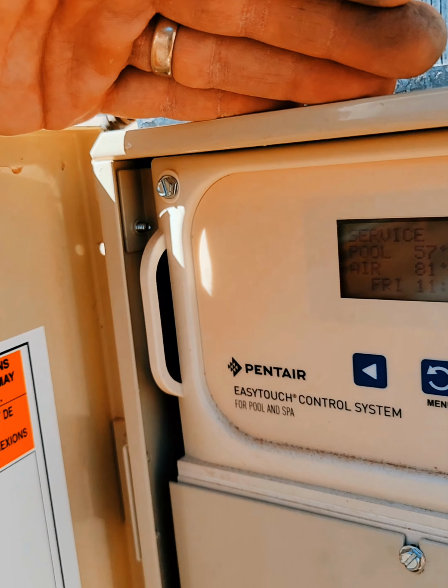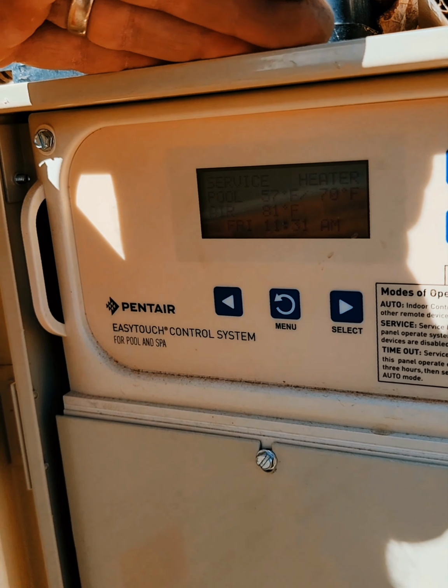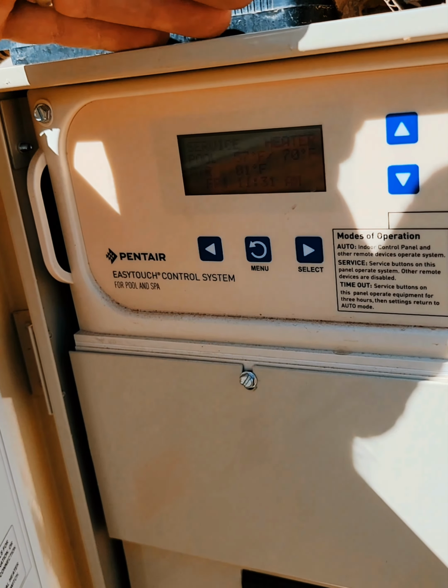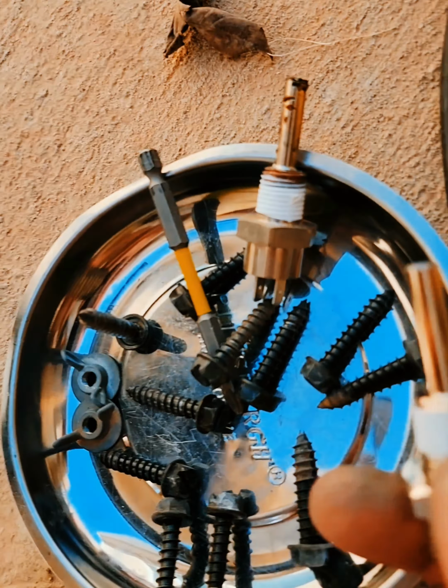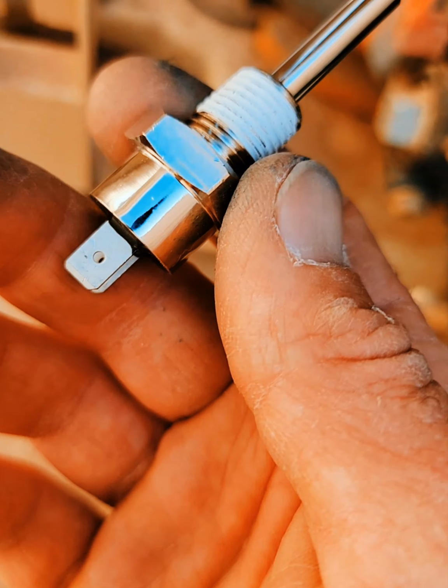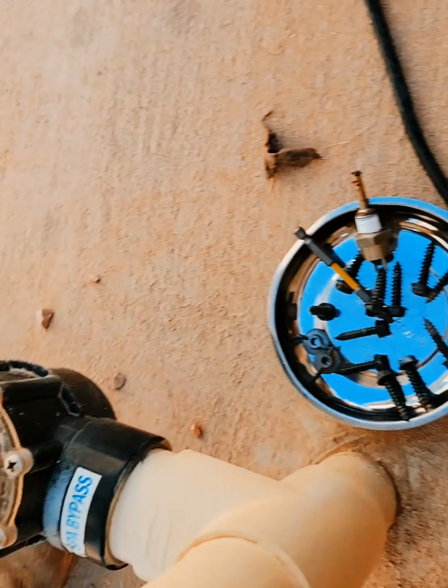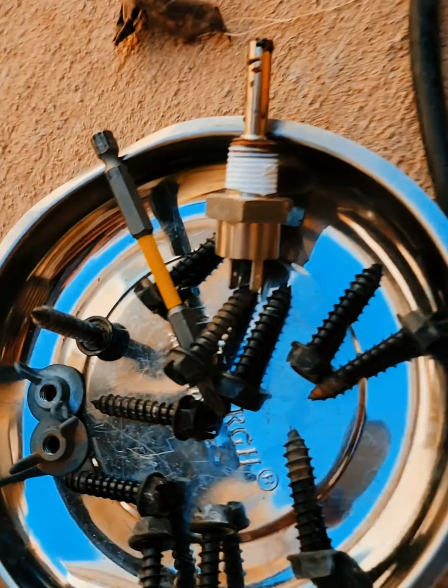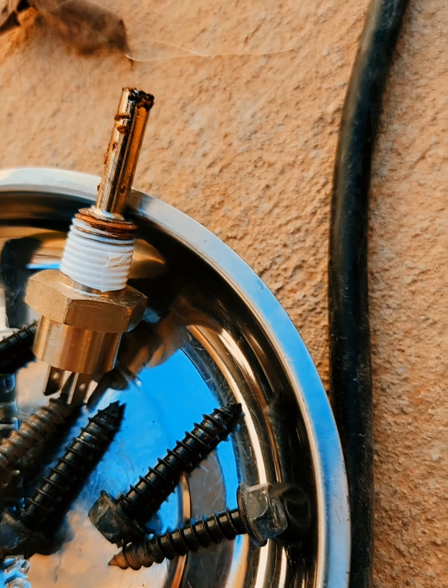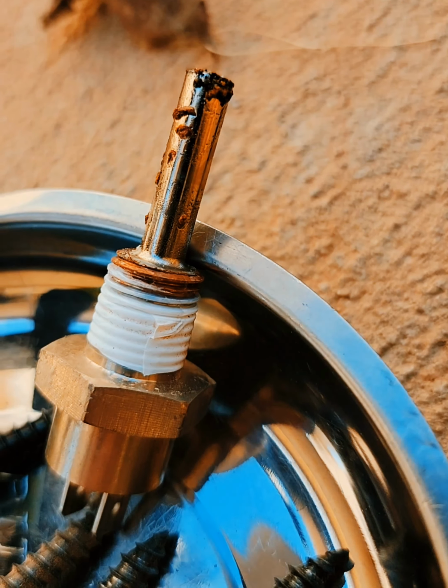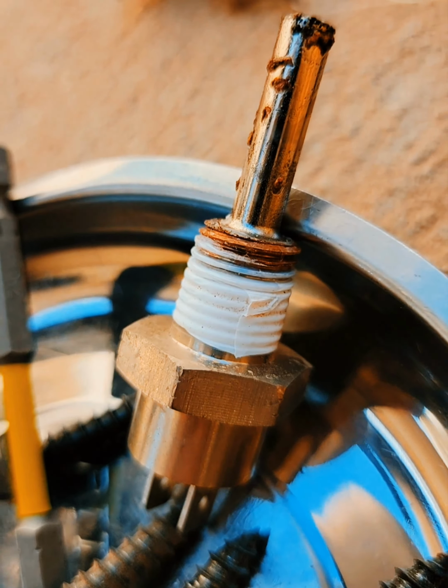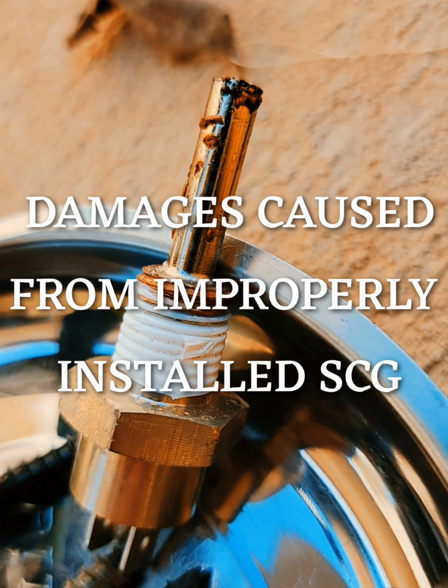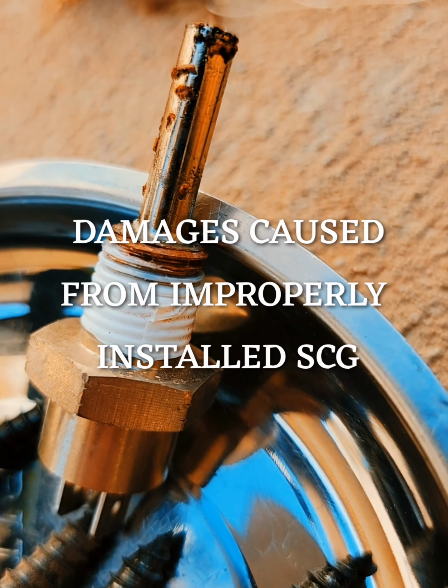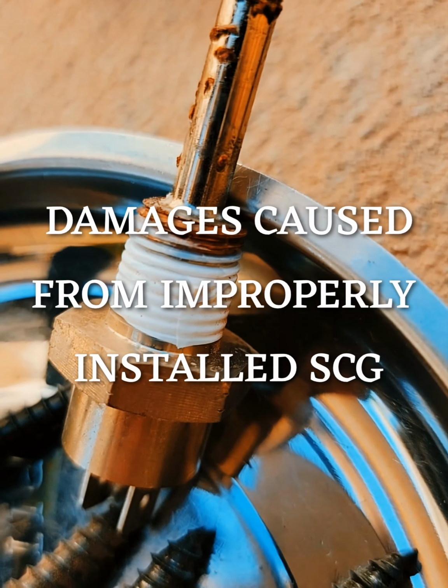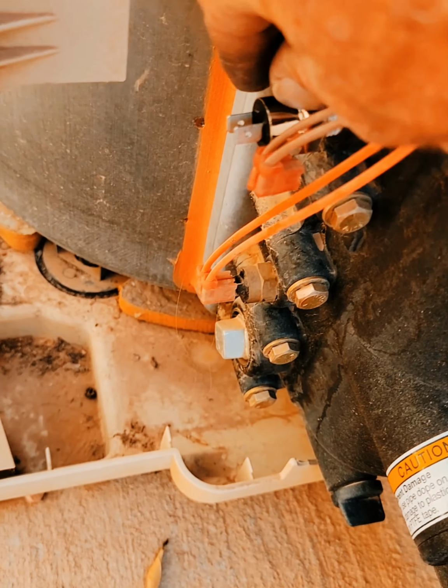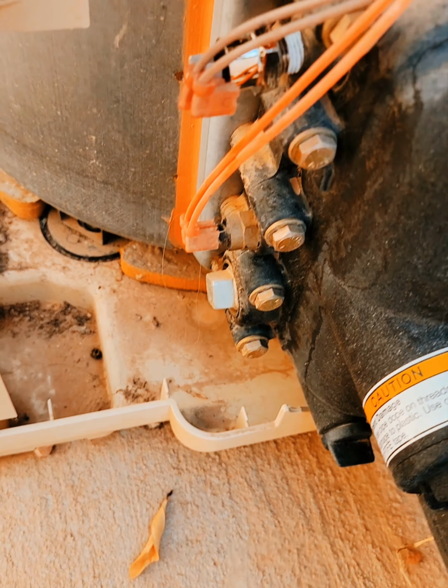Temperature's reading 57. Alright, well, I found out why temperature's all over the place. Look at that. So I'm going to put in this new thermistor right now. And while I screw that in, if you see all that corrosion there, that's going to be a result of really bad pH and alkalinity readings. I'll be checking that out after I get done.